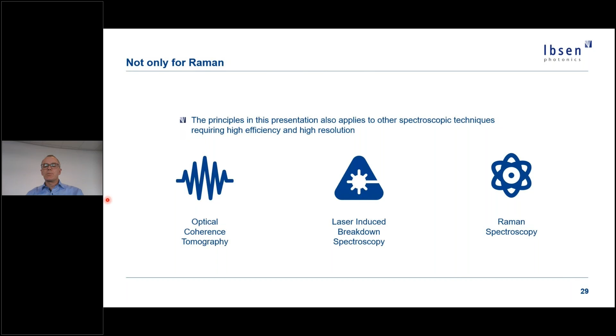So to summarize my presentation about using Raman spectroscopy beyond the lab, the key message is that there are a lot of very different requirements to the spectrometer when it should be used in an industrial environment compared to when the spectrometer is used in the lab. These requirements should be addressed by designing spectrometers tailor-made for the specific application. And this means making sure the spectrometer fits the exact wavelength range, matches resolution, size requirements, sensitivity, and noise requirements, all set by the application.